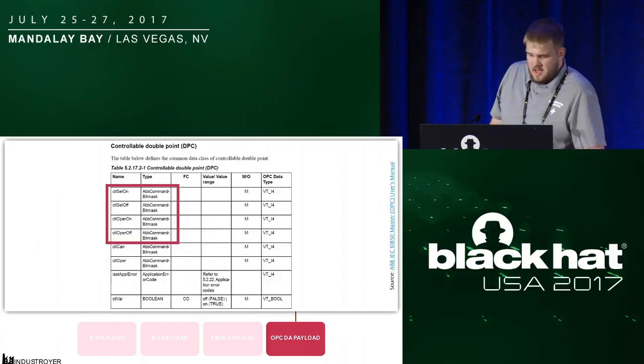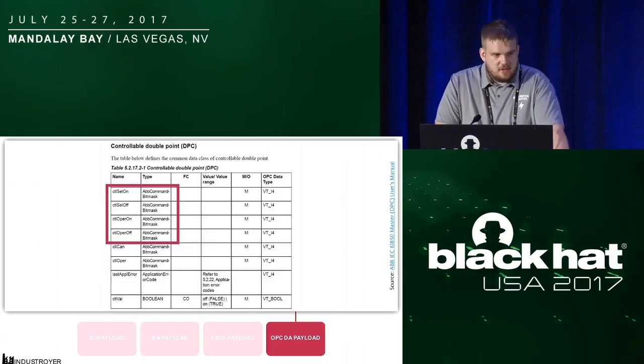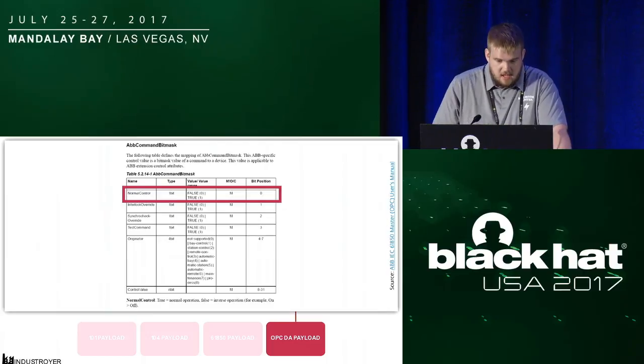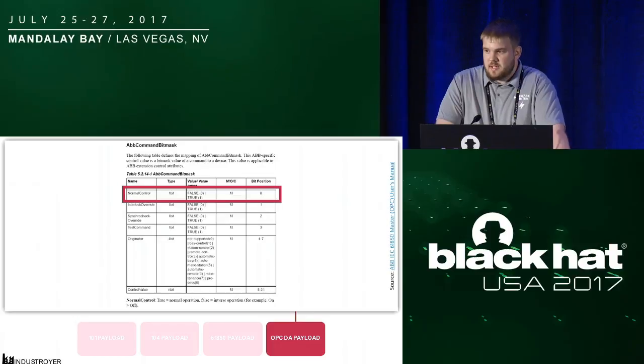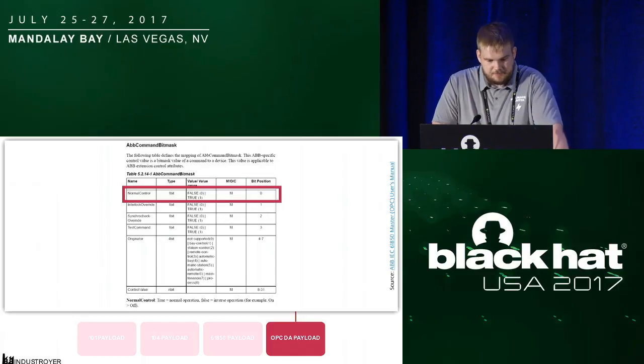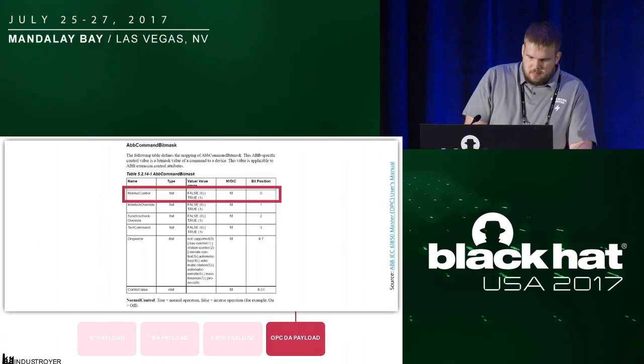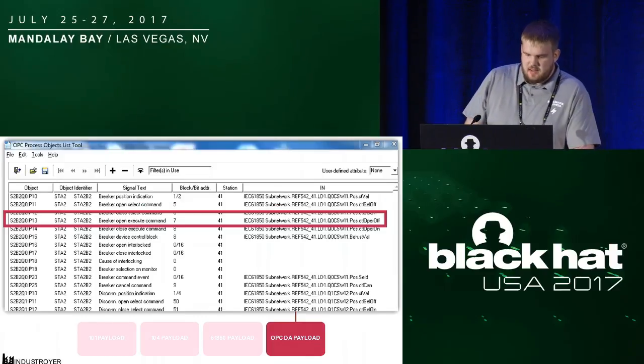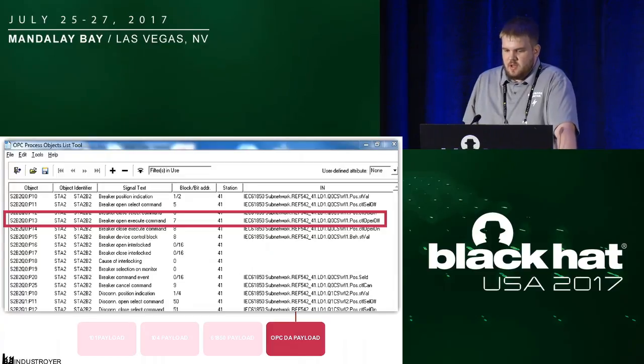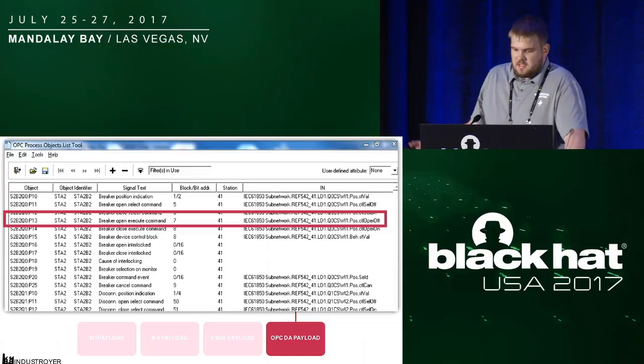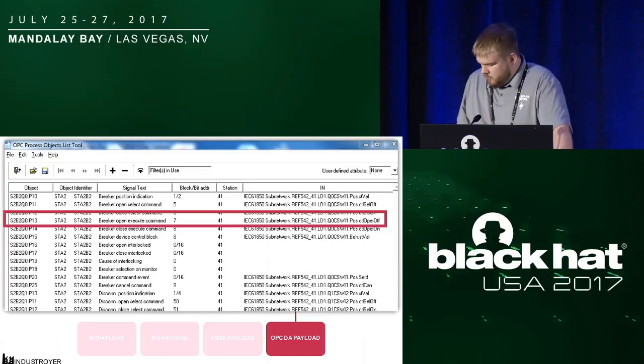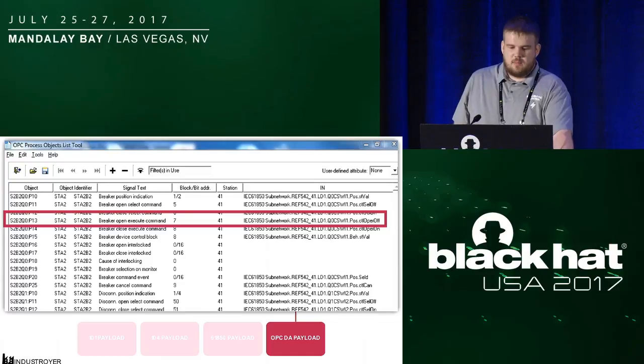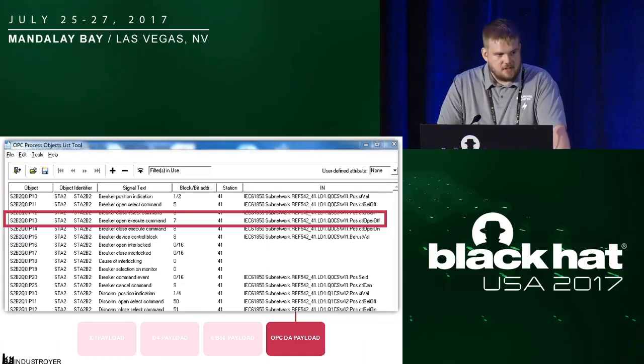Those tags are associated with ABB; their type is ABB command bit mask, and writing value 1 to bit position 0 results in normal execution of that command. This OPC process object tool by ABB helps us translate the commands into a more human-readable form. So again, the purpose is the same: opening circuit breakers.